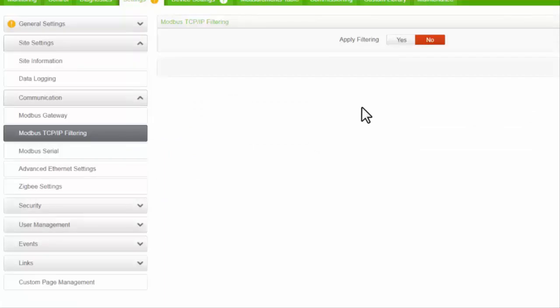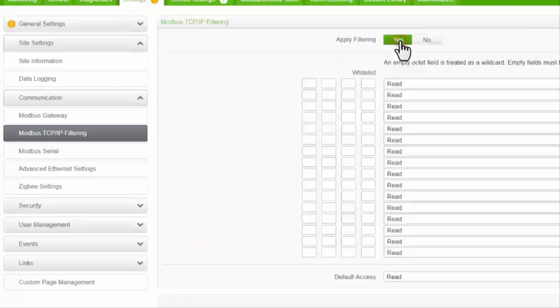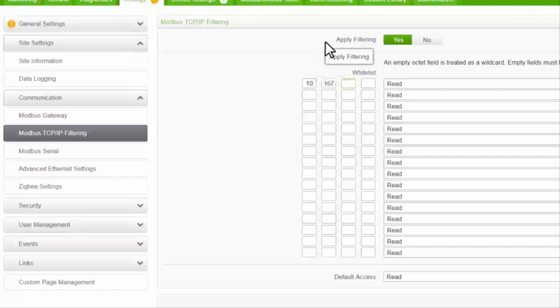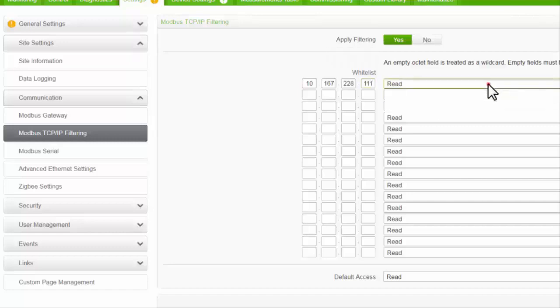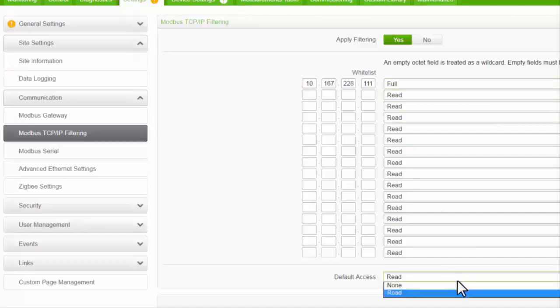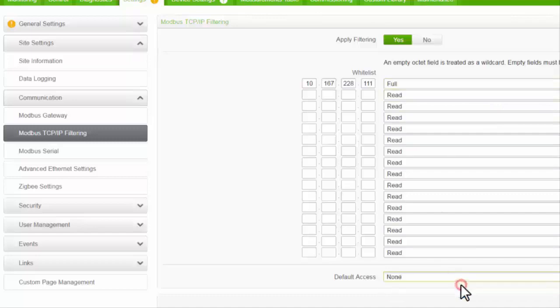You can use Modbus TCP IP filtering to minimize the number of IP addresses that can access the COMX and its downstream devices. This helps reduce the likelihood of unauthorized intrusion. We're going to enable filtering, change access for this device to full, and set access for all other devices to none.